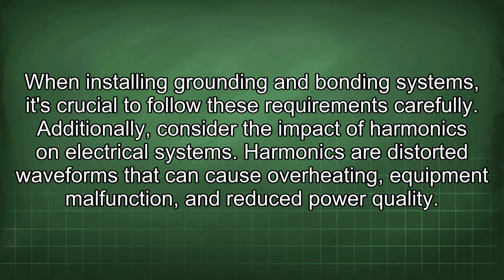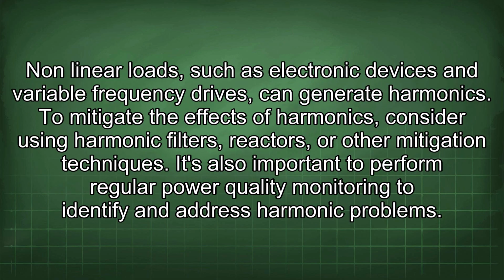Additionally, consider the impact of harmonics on electrical systems. Harmonics are distorted waveforms that can cause overheating, equipment malfunction, and reduced power quality. Nonlinear loads, such as electronic devices and variable frequency drives, can generate harmonics. To mitigate the effects of harmonics, consider using harmonic filters, reactors, or other mitigation techniques. It's also important to perform regular power quality monitoring to identify and address harmonic problems.